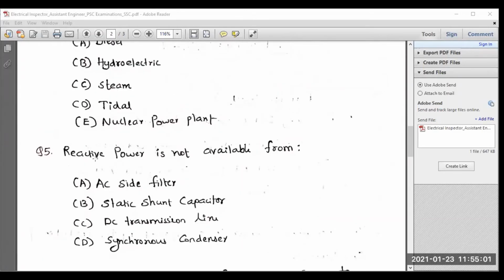Let me discuss another question. Reactive power is not available from: AC side filter, static shunt capacitor, DC transmission line, or synchronous condenser. Remember, reactive power is not at all associated with the DC transmission line. For a DC system, we don't bother about reactive power, so there's no need for any kind of reactive compensation. That is one of the advantages of the HVDC system.